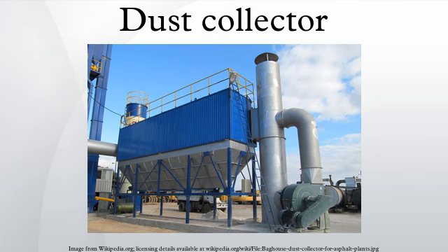In many cases, the heat or moisture content of dust can negatively affect the filter media of a baghouse or cartridge dust collector. A cyclone separator or dryer may be placed before these units to reduce heat or moisture content before reaching the filters. Furthermore, some units may have third and fourth stage filtration. All separation and filtration systems used within the unit should be specified.